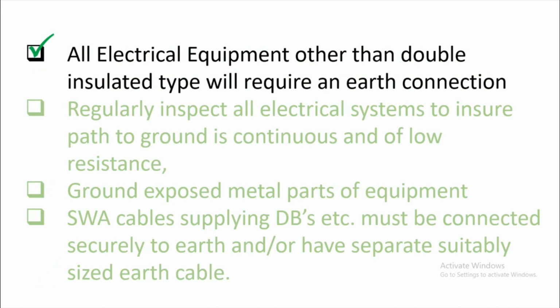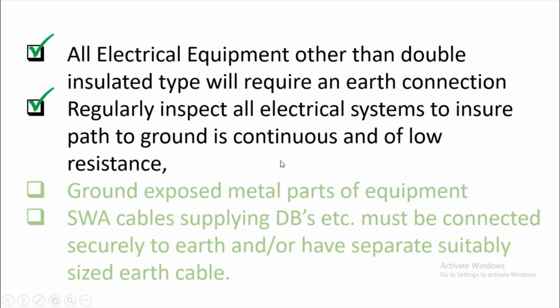All electrical equipment other than double insulated type will require an earth connection. So all electrical equipment should be connected to the earth connections. Regularly inspect all electrical systems to ensure the path to ground is continuous and low resistance. So when we are doing an inspection, the competent electrician is to ensure that the path of the electrical system to the ground is continuous.